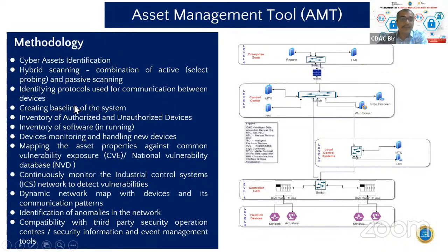Then we identified what protocols are supported. Suppose if we take an RTU, each RTU may support a different protocol. If you take some IED, it may support a different protocol. If you take RTU with IEC 60870 Part 5 104, we call it IEC 104 - which protocol is it following? Is it following Modbus? Is it following DNP3 or anything? What protocol is running on that particular device? Otherwise, if it's a PMU, what is IEEE C37.118? What protocol does it belong to?